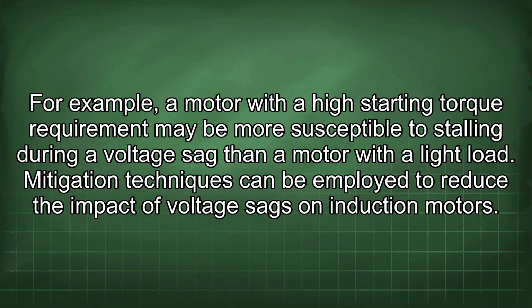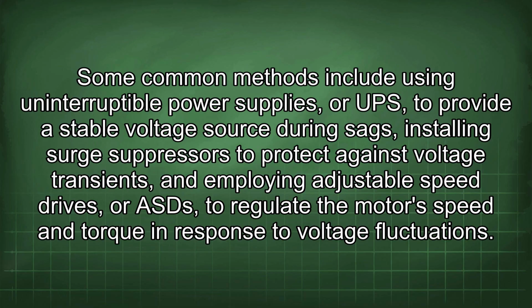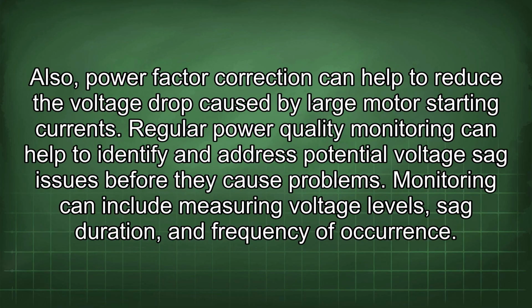Mitigation techniques can be employed to reduce the impact of voltage sags on induction motors. Some common methods include using uninterruptible power supplies, or UPS, to provide a stable voltage source during sags, installing surge suppressors to protect against voltage transients, and employing adjustable speed drives, or ASDs, to regulate the motor speed and torque in response to voltage fluctuations. Also, power factor correction can help to reduce the voltage drop caused by large motor starting currents.